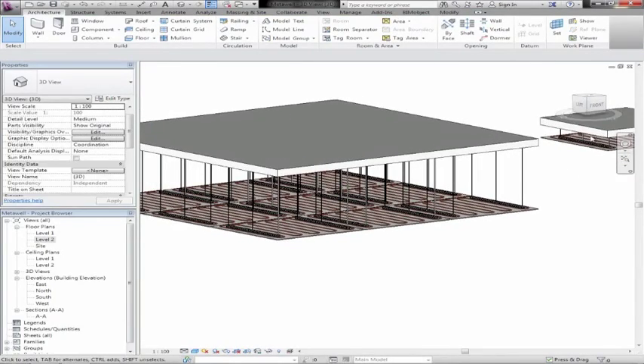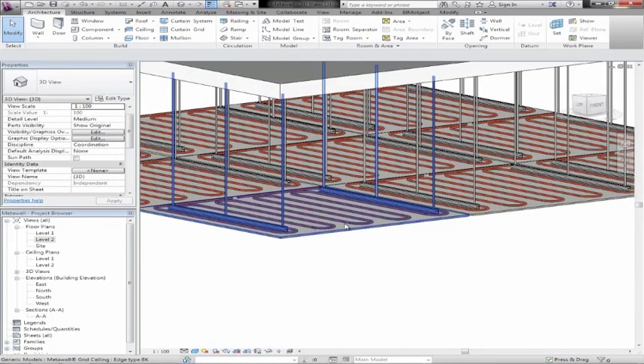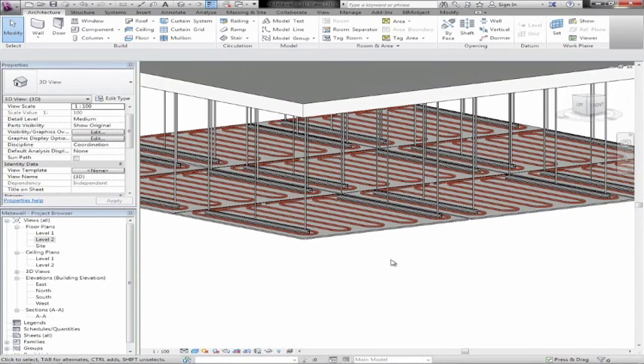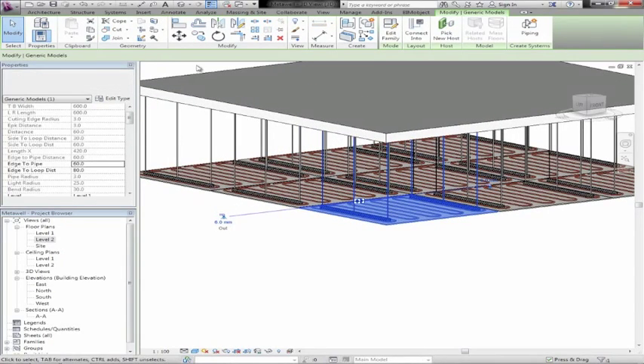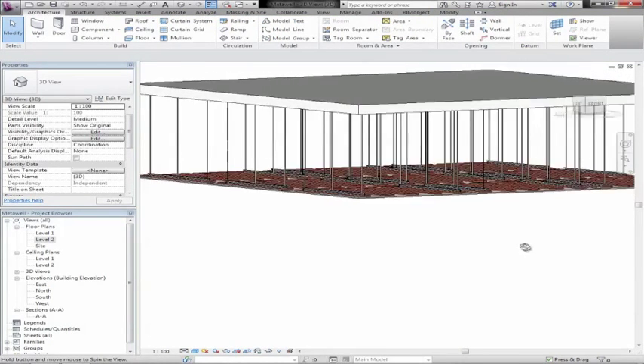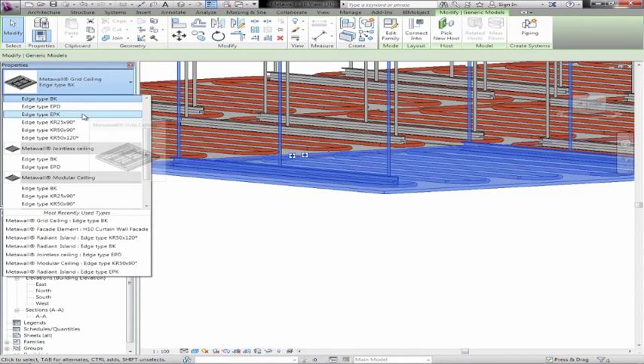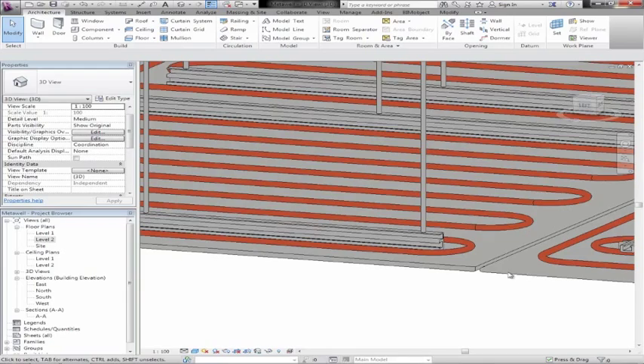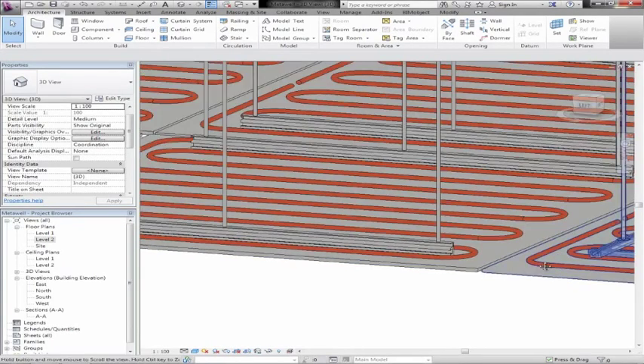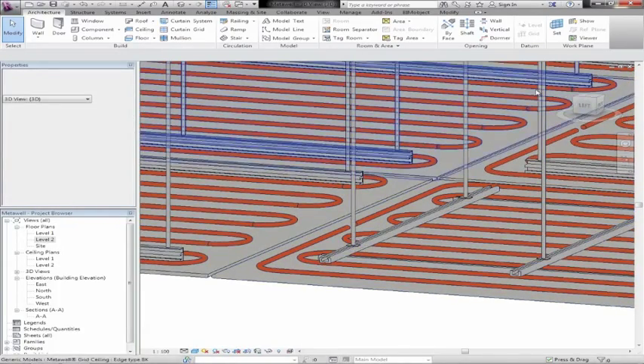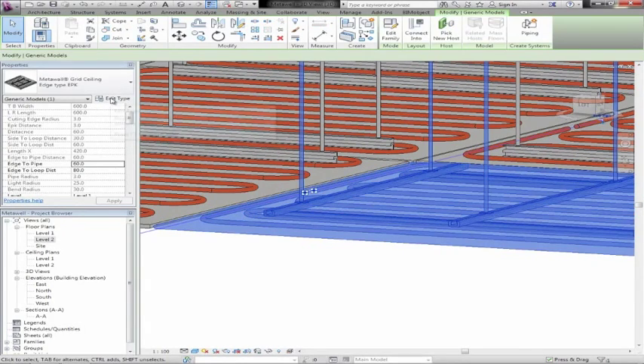As you can see, these are radiant ceilings, which means they can be heated and cooled. We have all of the piping here, and we've done them as system elements in Revit, which means HVAC consultants using these objects can connect their pipes directly to the piping. We know where all the piping is going from — all of the cold and warm water. We also have different edge treatments. If we change this to an EPK, we see that we have a rounded edge on the ceiling. You can see the difference between the BK and the EPK, and we have different support systems as well.